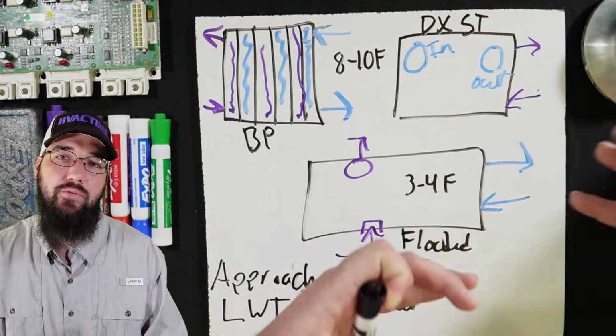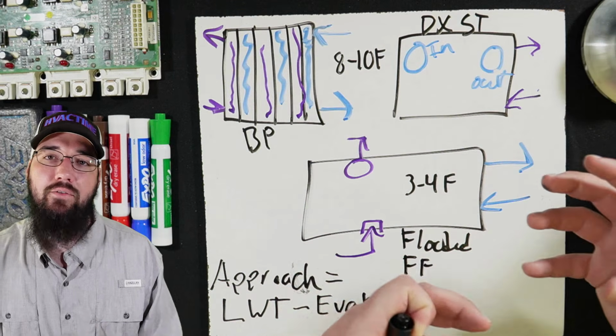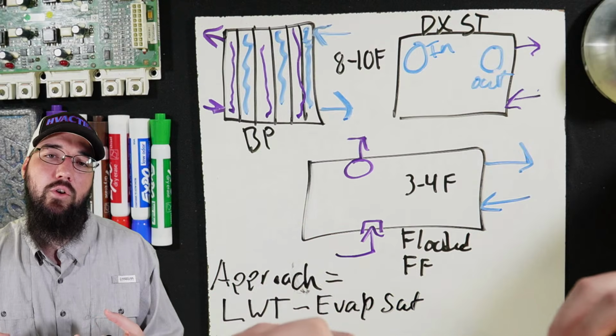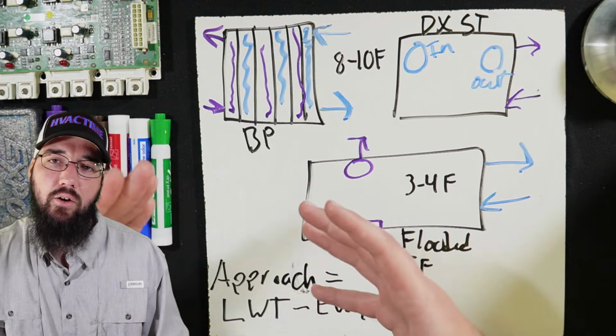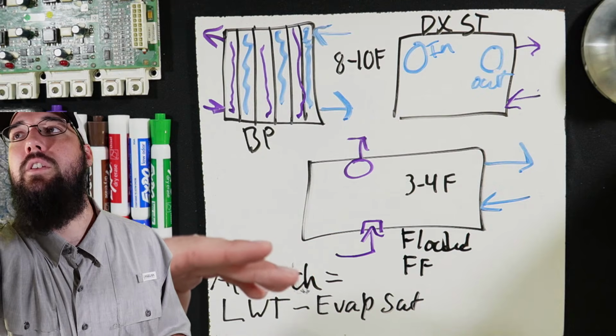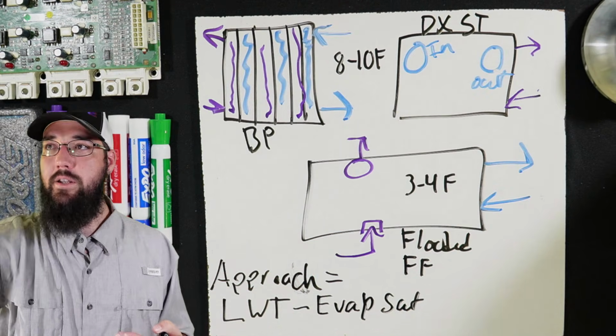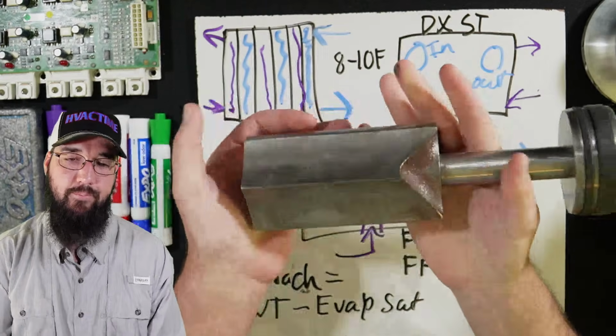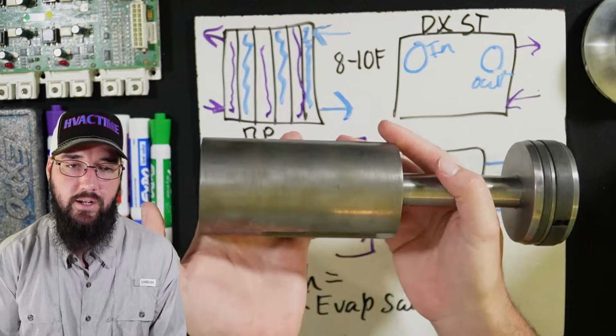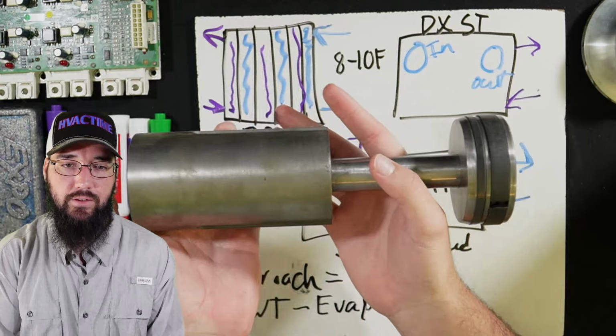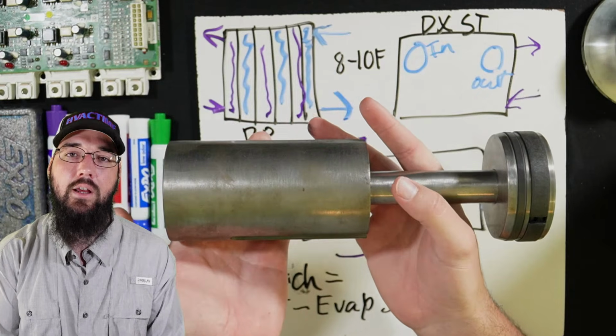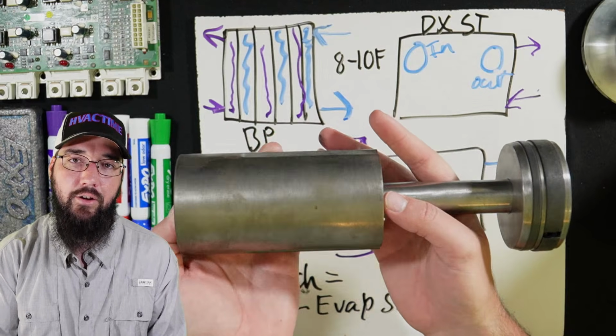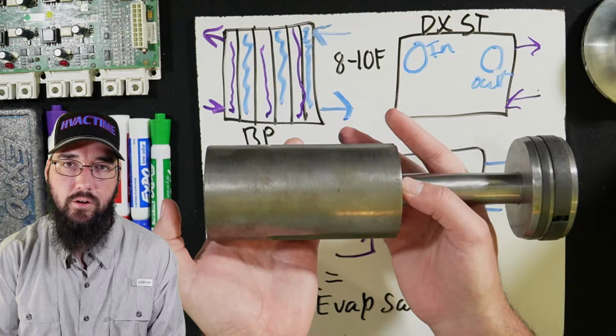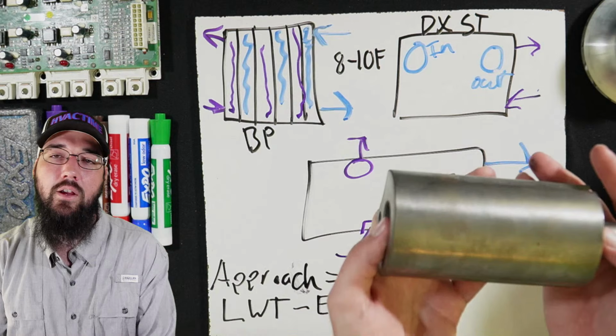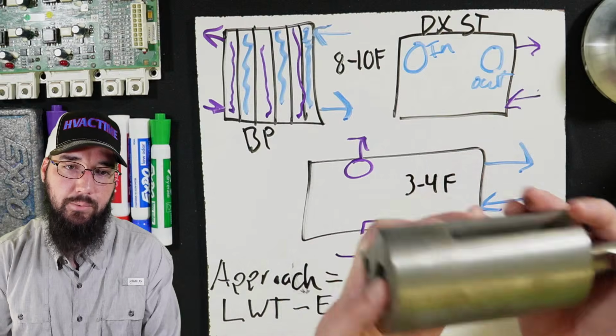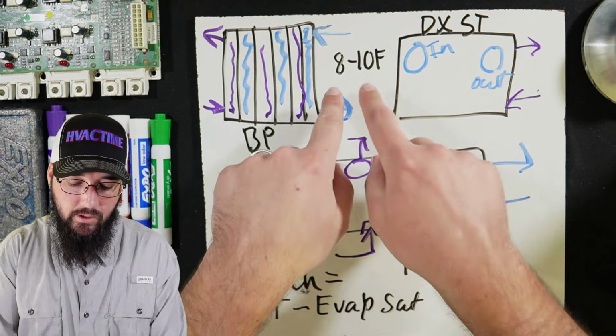Let's say a screw compressor follows the compressor slide valve or speed. Okay, so as the slide valve loads the machine. If you don't know what that looks like, do I have one sitting right here on my desk? I absolutely do. So this is what your slide valve is going to look like inside of there, or a version of one. As this is sliding into a loaded position, the motor current is going to follow that and increase because the compressor is doing more work. As we unload the slide valve, compressor does less work, motor current drops. All right, you've got the basic concept.